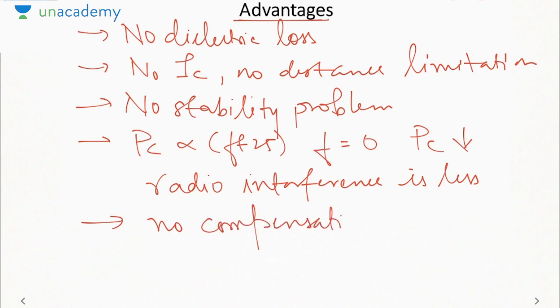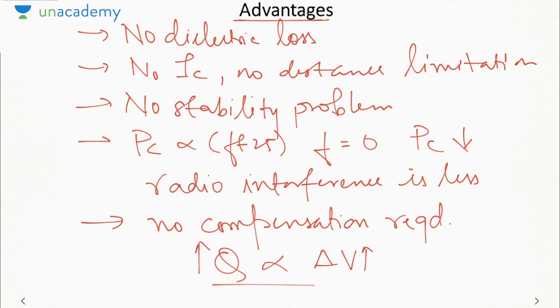See, in case of AC transmission, what was happening? If you were drawing more reactive power, then the voltage will get reduced, because Q is proportional to delta V. If Q increases, voltage drop increases. But in DC, there is no concept of reactive power, and hence no reactive power compensation is required. But yes, reactive compensation is required at the terminals or at the converter end, because the converter requires reactive power, which will be supplied by the compensator. But you need not do reactive power compensation at the midpoint or at any other point on the transmission line, because there is no concept of reactive power flow in HVDC transmission.